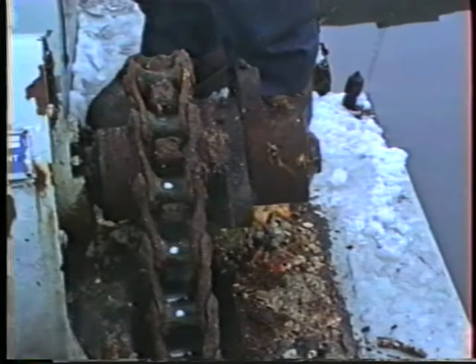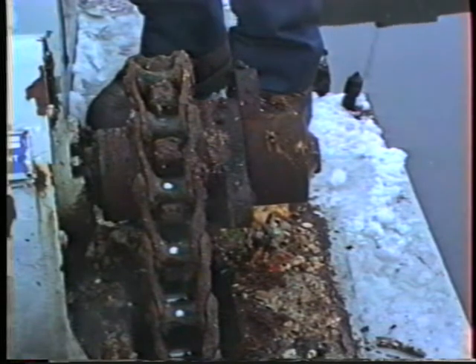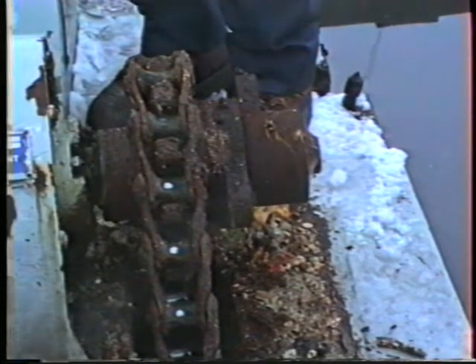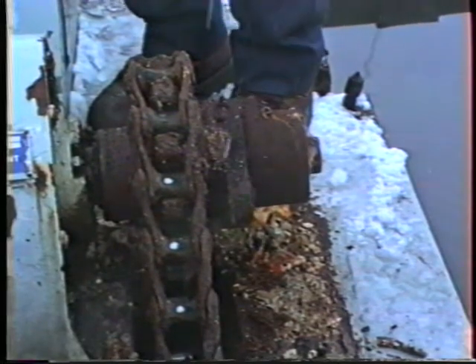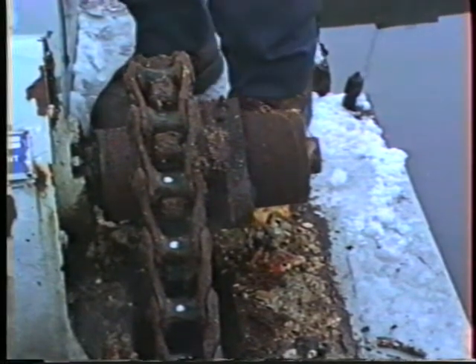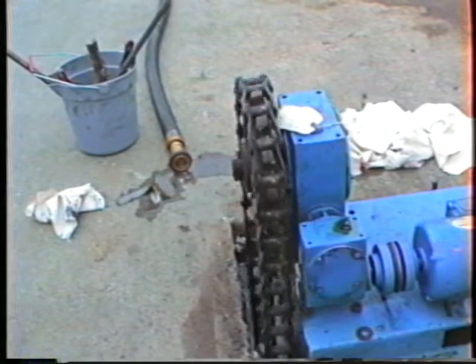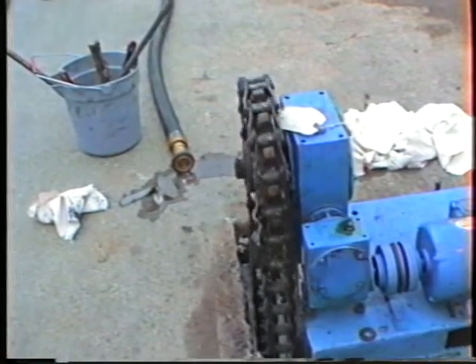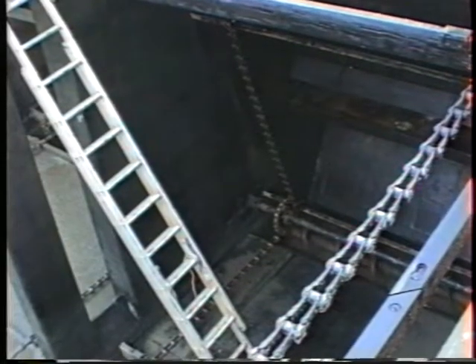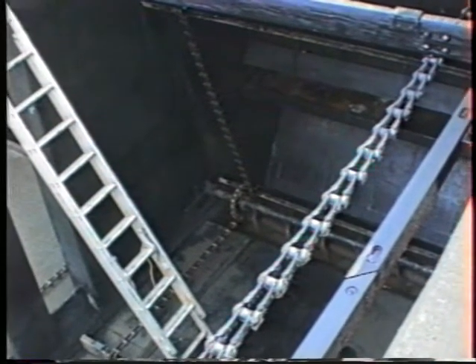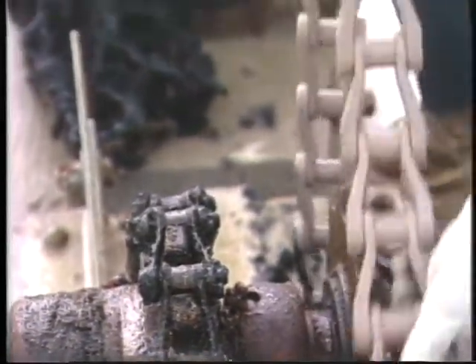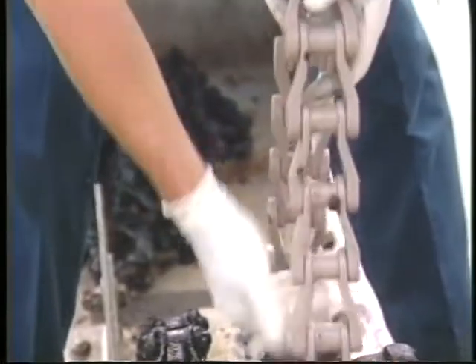If the motor and the gearbox run, but the collection mechanism does not, it could indicate that a shear pin or chain may be broken. To determine what the problem may be, observe the drive chain. If the drive chain is moving and the collection system is not, it probably indicates a broken chain on the collection mechanism. When the drive chain breaks, it may be missing altogether.